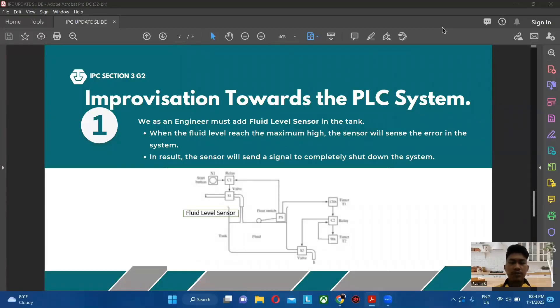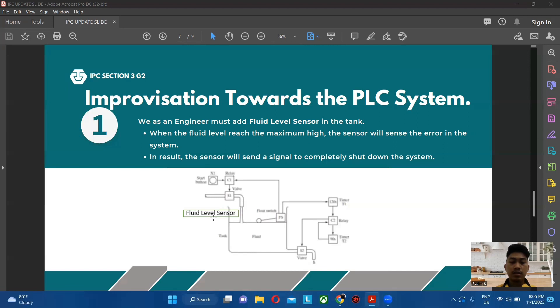Hello and good day everyone. My name is Muhammad Syafiq bin Qasmazuli and I will continue the presentation on the improvisations towards the PLC systems. Our group has two suggestions to improve our PLC system. The first one is to put another fluid level sensor inside the tank, located at a certain maximum high level — higher than the normal level at the fluid switch. Whenever the fluid switch has problems and the S1 valve is still running, when the fluid level reaches the maximum high level, the sensor will sense the error and send a signal to shut down the system.